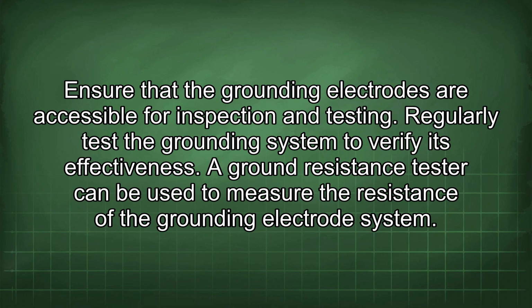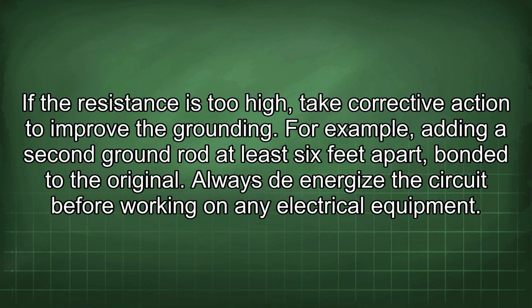Regularly test the grounding system to verify its effectiveness. A ground resistance tester can be used to measure the resistance of the grounding electrode system. If the resistance is too high, take corrective action to improve the grounding. For example, adding a second ground rod at least 6 feet apart, bonded to the original.